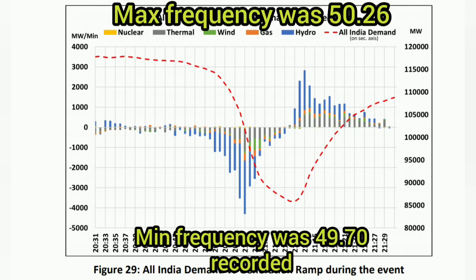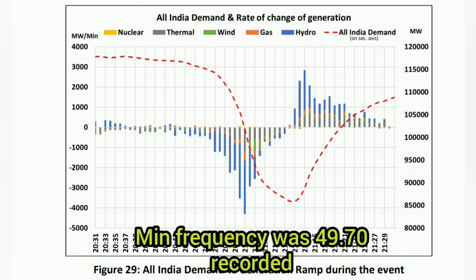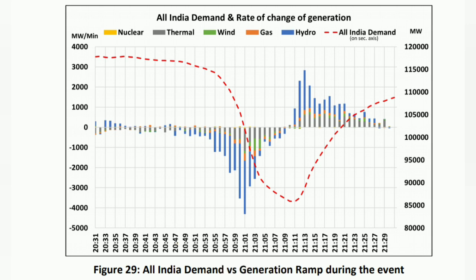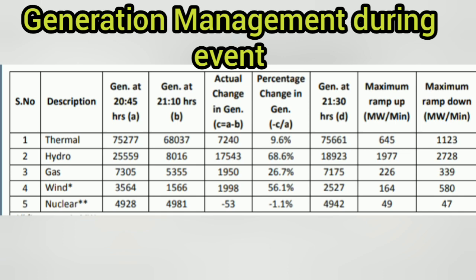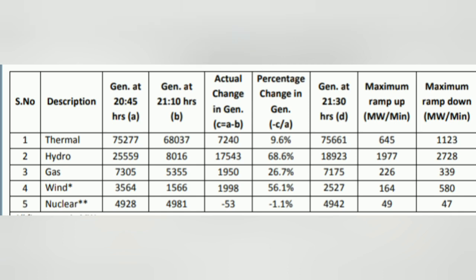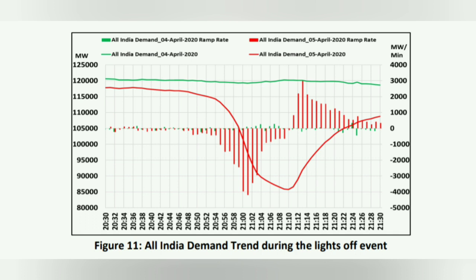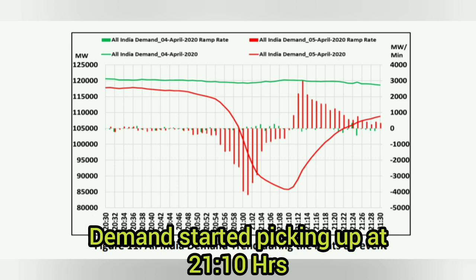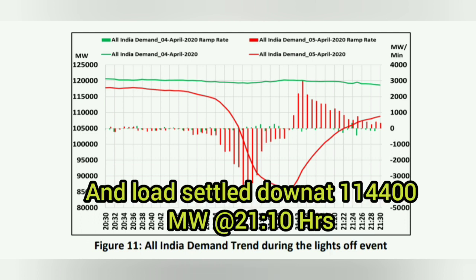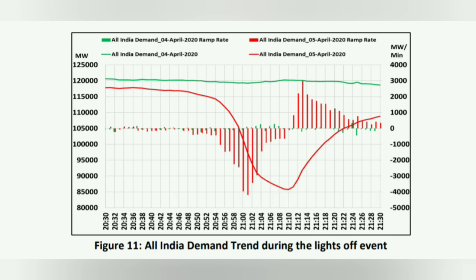The grid frequency during the event remained in the range of 50.26 Hz to 49.70 Hz, with maximum frequency of 50.259 Hz and minimum frequency recorded at 49.707 Hz. All India demand started picking up again at 9:10 p.m. and settled around 1,14,400 megawatt. This recovery was again managed with increased hydro, thermal, gas and wind generation.